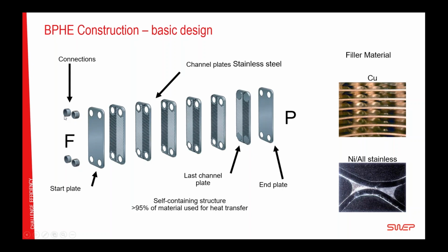You put the kind of connections you want, and in this case, you see that both the start plate has 4 holes and the back plate has 4 holes. This is normally not the case. You don't want the flow to go inside and out the backside before passing the heat exchanger. But this is to indicate that you can put the connections on the front side or the back side, or the hot side on the front side and the cold side on the back side, or whatever combination thereof.